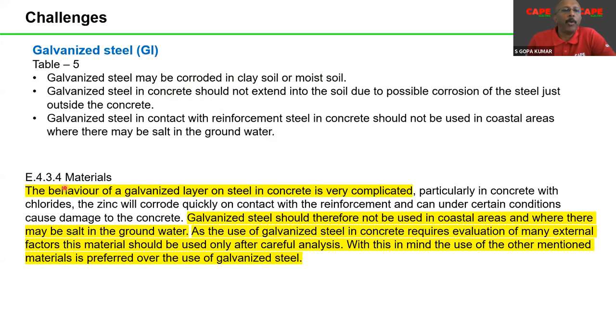In clause E4.3.4, materials, the behavior of galvanized layer on steel in concrete is very complicated. I will just read the explanation which is highlighted. Galvanized steel should therefore not be used in coastal areas and where there may be salt in the groundwater. That is one point. The second is, as the use of galvanized steel in concrete requires evaluation of many external factors, this material should be used only after careful analysis.